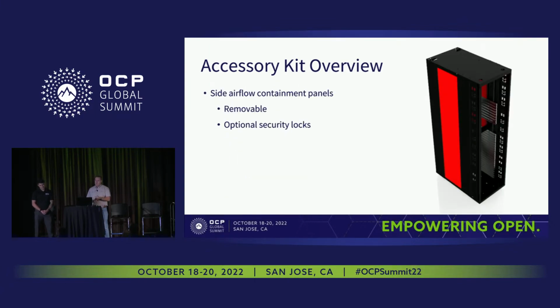The first one is the side airflow containment panels. These would typically be used within our data centers on an end-of-row application. With this particular kit, it's the same panel, can be used on the left or right side of the rack. They are removable, so they toe in at the bottom, screw in at the top. There may be some use cases, perhaps at a co-location site, where we need to restrict access to the rack, provide a little bit additional security measures. So we do have an option to add security locks to these panels if we need to restrict access to those.